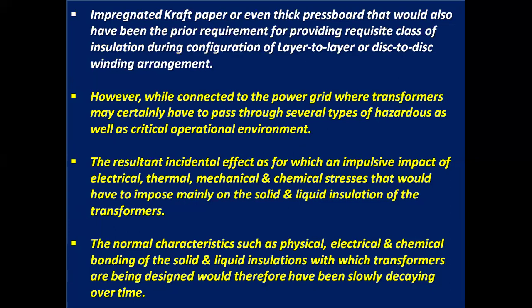However, while connected to the power grid, transformers have to pass through several types of hazardous as well as critical operational environments. The resultant incidental effect is an impulsive impact of electrical, thermal, mechanical and chemical stresses imposed mainly on the solid and liquid insulation of the transformers. The normal physical, electrical and chemical characteristics of the solid and liquid insulations with which transformers are designed therefore slowly decay over time.